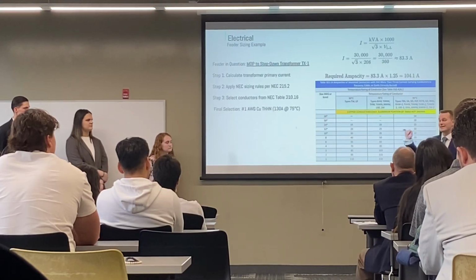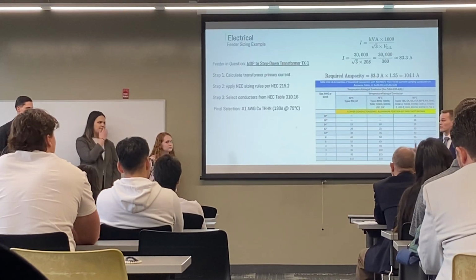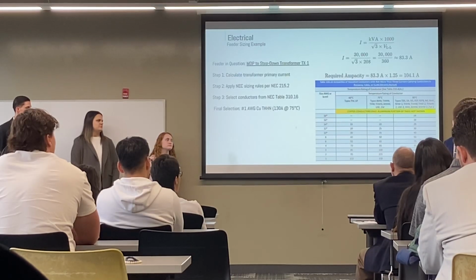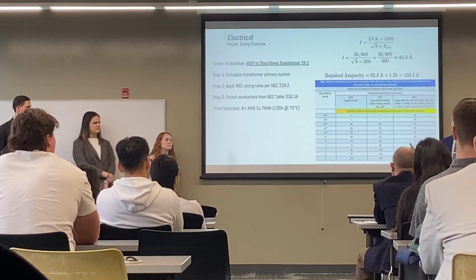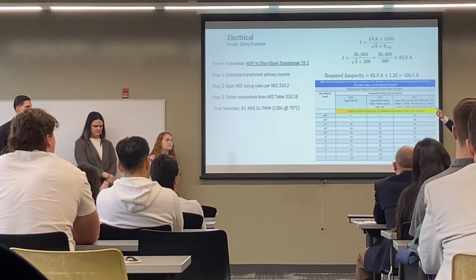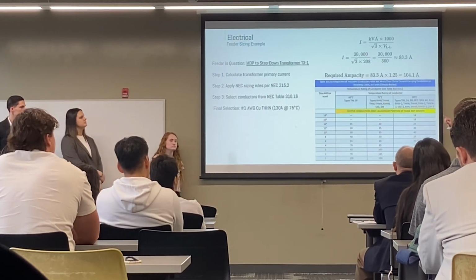But then according to NEC 215.2, which is the National Electric Code, if it is a continuous load, which means it can be running for most likely longer than 3 hours continuously, you need to multiply that by 125%. So we take that number times 1.25, and get 104.1 amps.